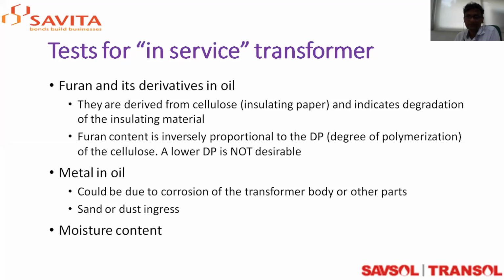the paper will absorb moisture, taking it up from the oil into the cellulose molecules. At high temperature, moisture and cellulose react, and the cellulose molecule breaks down, forming furan. This furan then moves from the paper into the oil. Because of this transfer of furan from paper to oil, aged oil will show furan content, and from that furan content one can interpret the futuristic life of the transformer.